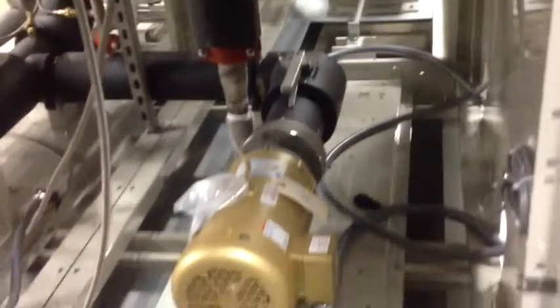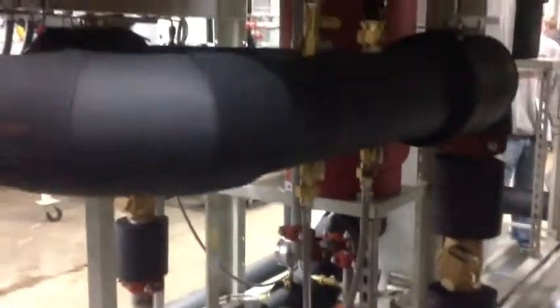In the background, you can see on the left the green cap on the 5-gallon glycol mini feeder and the red bladder type expansion tank. In the background, you see the plate and frame heat exchanger. As we pan down and move to the left, you can see 2 differential pressure switches adjacent to the pump on the left-hand side. Those provide a redundant proof of flow for switching from the primary pump to a backup if necessary.